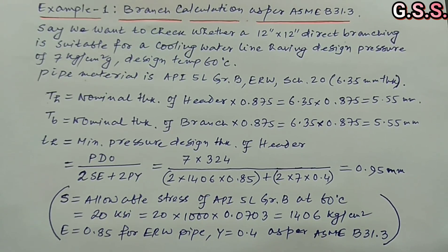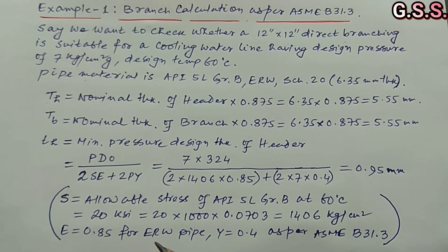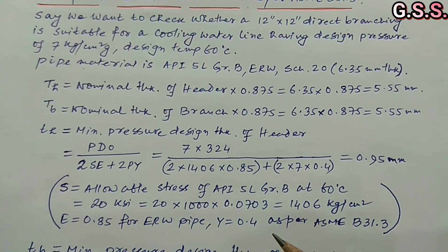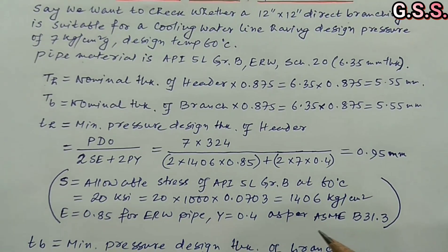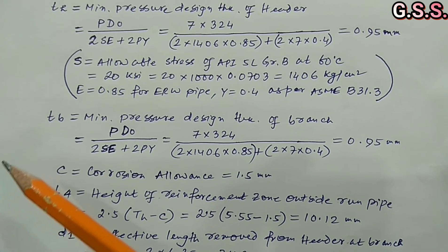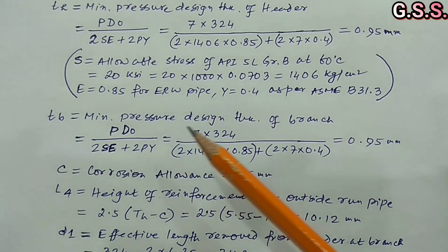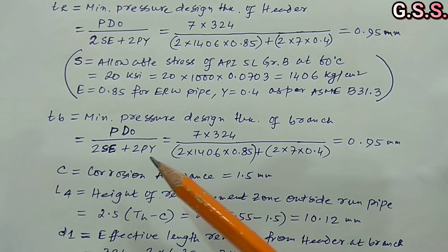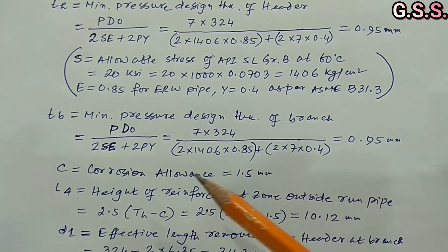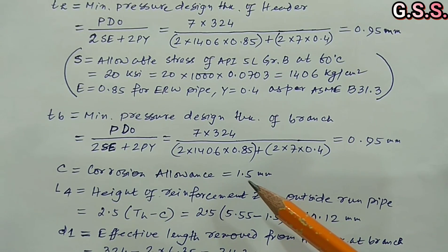E = joint efficiency = 0.85 for ERW pipe. Y = 0.4 as per ASME B31.3. Similarly, small tB = minimum pressure design thickness of branch = 0.95 mm. C = corrosion allowance = 1.5 mm.